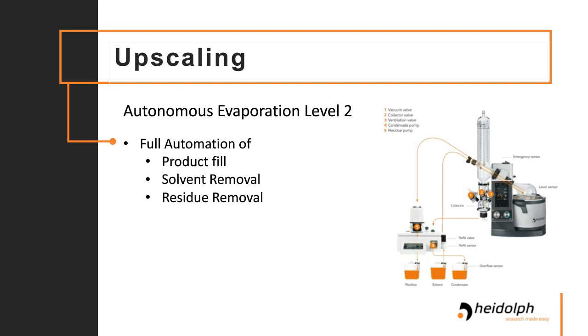The advantage of this module is that you don't need to be at the rotary evaporator. It can automate your evaporation process, and you can collect several liters of a specific mixture in a vessel and evaporate it in one process, even overnight or over the weekend. It also guarantees that the filling level of the evaporation flask stays at the most efficient level, since usually when you start evaporation there's too much liquid, making the process less efficient.